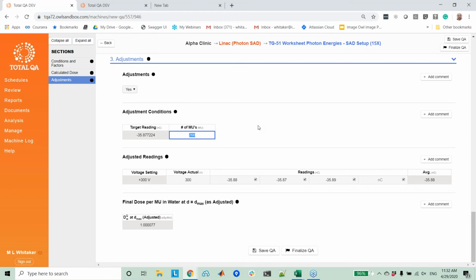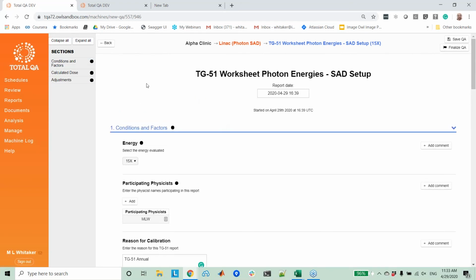But if you're choosing to do adjustments, you can set the number of MUs. I actually put it to 200 here just to illustrate that. Then it'll scale the target reading appropriately to the number of MUs you have in here. Then you do the readings, average, and it gives you a final dose. At that point, once you're done, there are a few little indicators on the side here. Once these dots all get filled in, it's all filled out. You can adjust the report date if you need to.